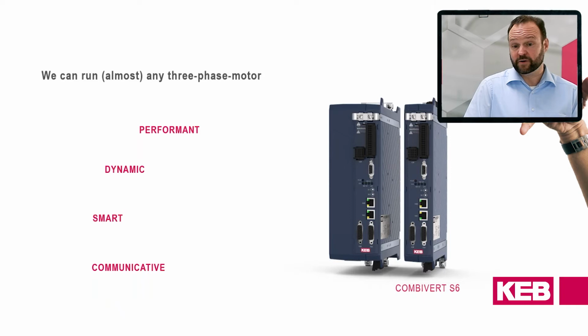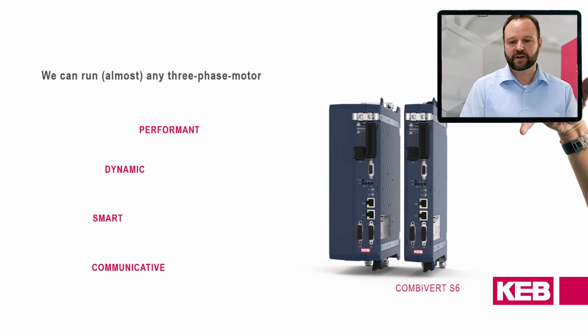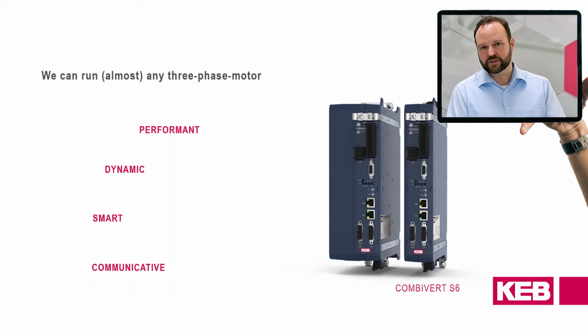Then we're talking about encoders. All the motors, or most of the motors, need encoders, or many of them. Also there, we can handle a big variety like incremental encoders, TTL, HTL, resolver, analog sine cosine, digital encoders like Hiperface, EnDat, or BiSS. And of course, we are also very good in running motors encoderless, controlled encoderless. And all these functions are switchable.